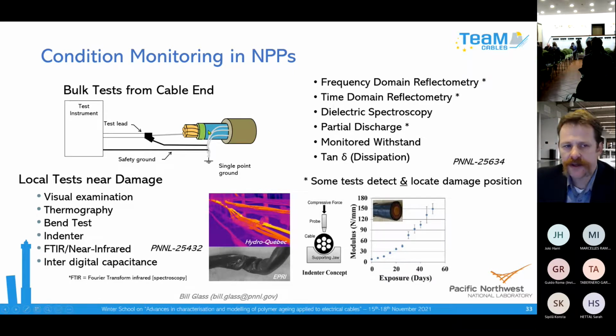The trend is really towards reducing the labor involved. For instance, if you can avoid disconnecting the cables from motors before testing them, that will save much labor in the testing. Ultimately we need to move towards online testing, where we don't disconnect the cables at all, and we continually monitor the cable health over the operation of the plant, not just during some little time stamps during the outage.